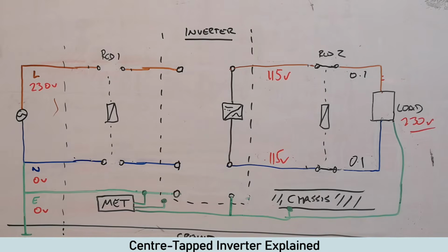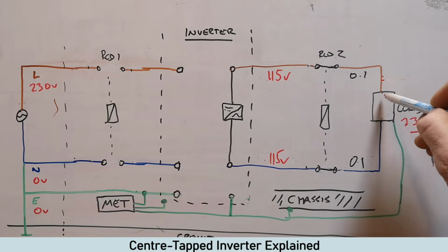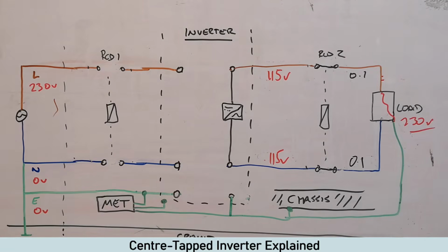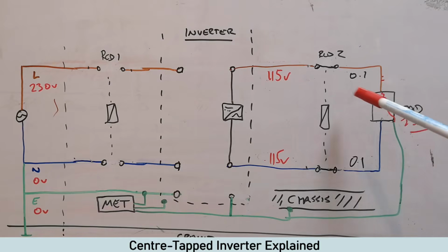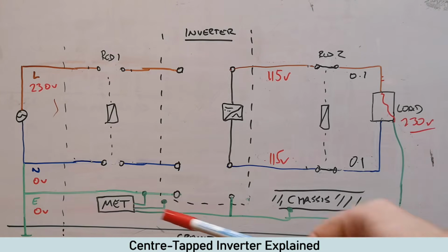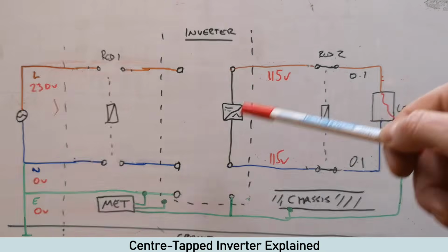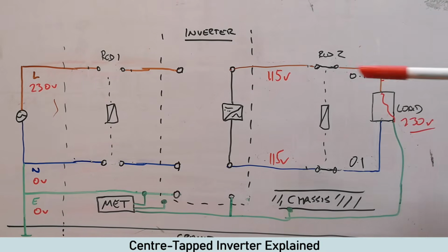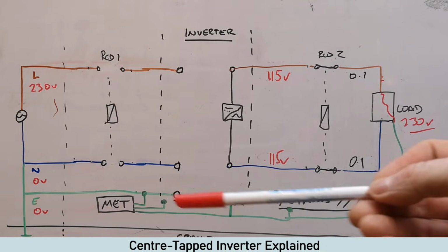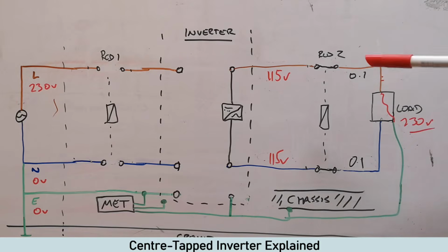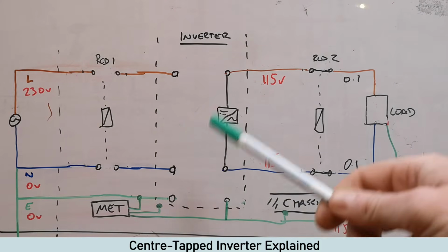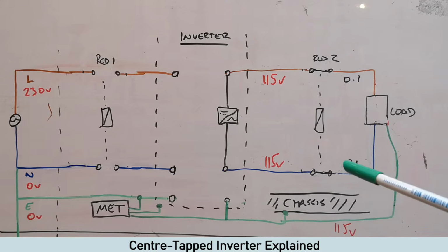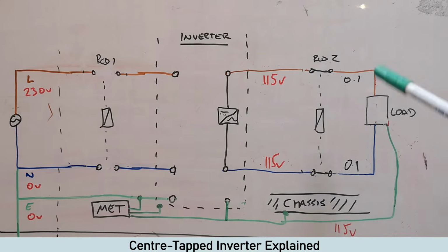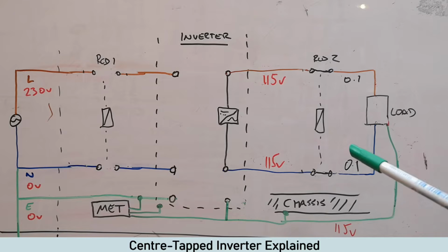So what happens now if there's an earth fault? Let's say the appliance has an earth fault. It's got a metal casing. The earth's obviously on the casing. It's going to flow down here, but obviously now there's no way back. So what's actually going to happen here is this earth system is going to be at the same potential as that live. So with a floating system or center tapped floating system, it is incredibly safe because you've not actually got a fault path, which obviously introduces shock risk.